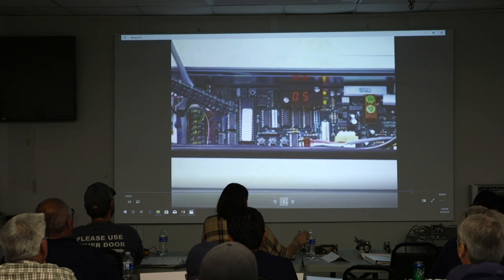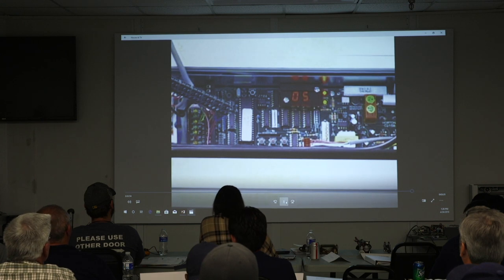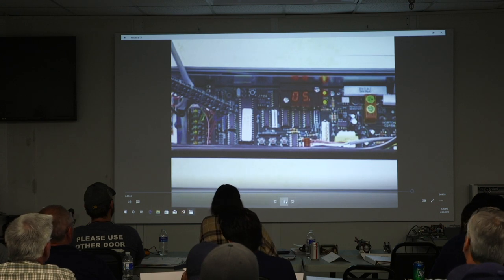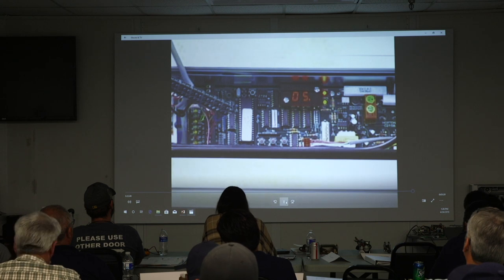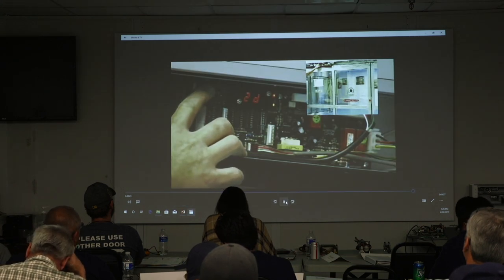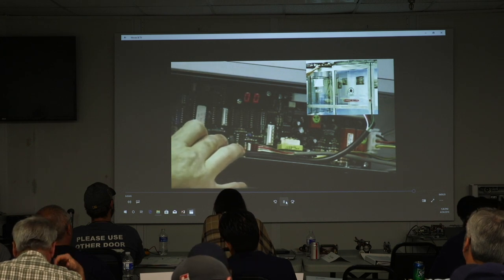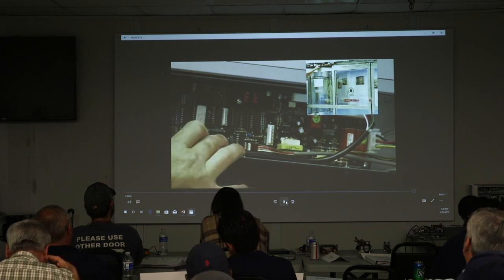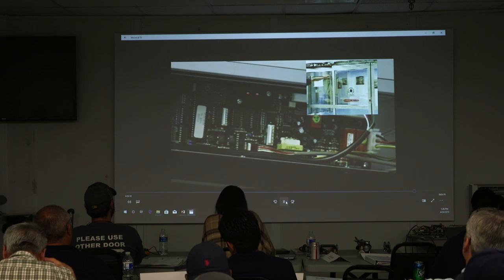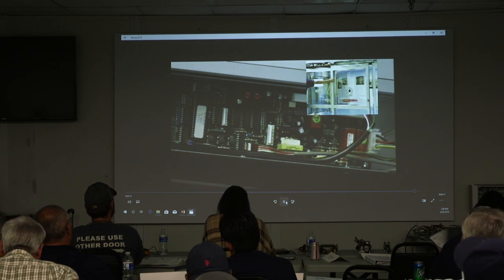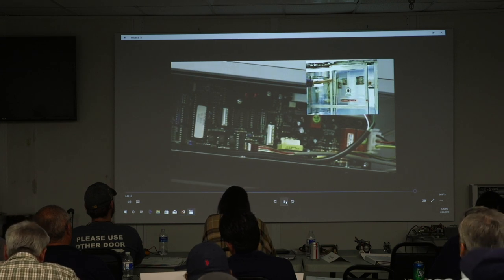The C2150 control depends on the encoder for information on door location, direction, and speed. Encoder diagnostic is available to test encoder function. To perform encoder test, press reset and down together. Release reset, display should show 10, then double 0, followed by ET for encoder test. One segment from each display should display.